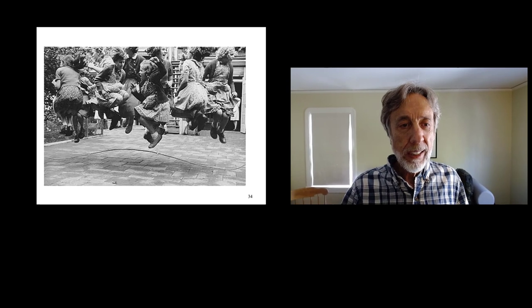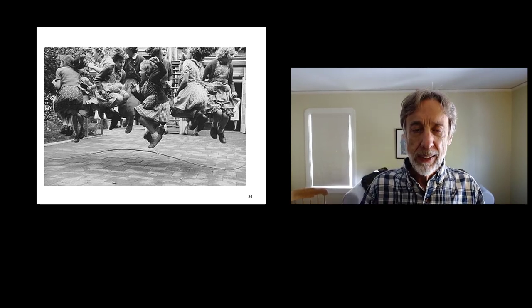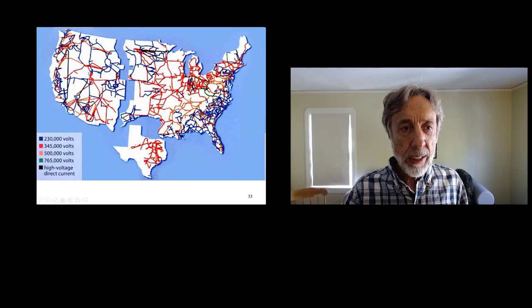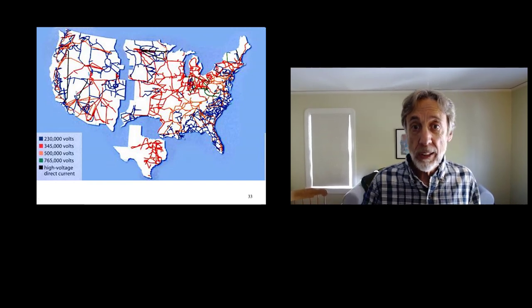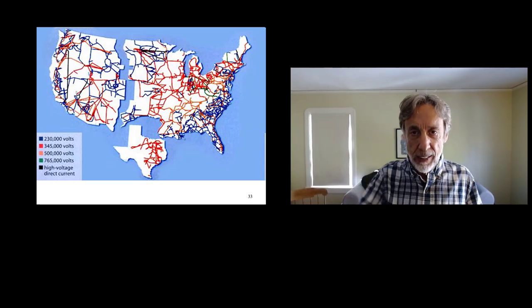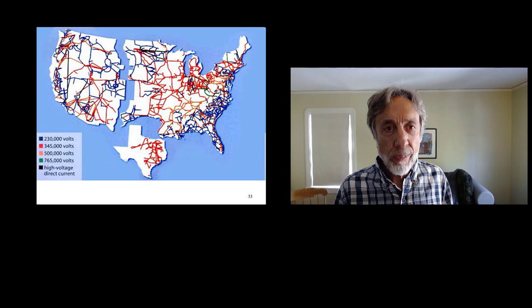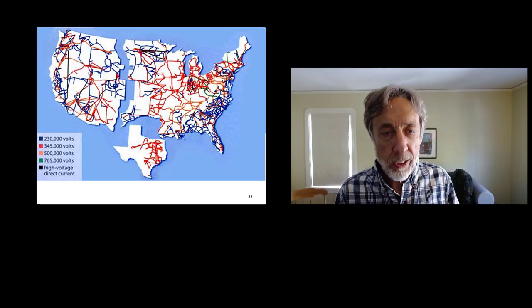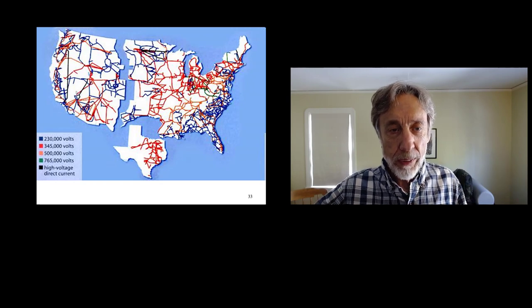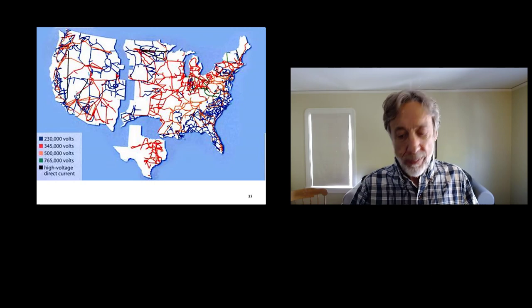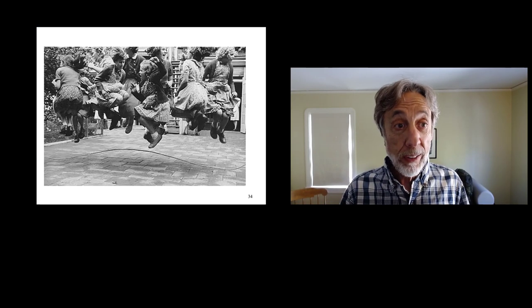Why? Because these cycles of the power going back and forth are measured, and normally in the grid they're running at about 60 cycles per second, 60 round trips per second. The different grids have all of their power plants in sync. They're all moving around in the same cycle to the extent that there are power plants that use a turbine. The turbines are spinning at the top and the bottom at the same time, regardless of where they are within the interconnection. So there's a certain frequency, a certain cycle to the power in the western interconnection or in the eastern interconnection. And you can't take power and move it directly from one cycle to another interconnection with a different cycle, because if you did that, then you're likely to trip up the system and you might cause a major power outage in one place or another.